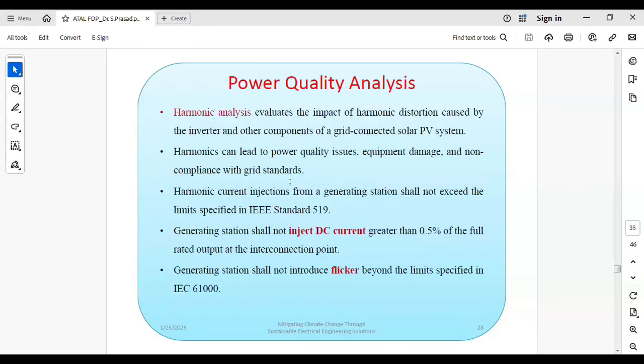And then the next study is power quality analysis. Third one, power quality analysis. Just briefly I'll tell you, due to shortage of time. This is also one of the most important tasks performed by a power engineer whenever the RE developer is going to install a PV plant which will be connected to the grid. So at the point of interconnection, how much harmonics you are injecting into the grid, that has to be verified. A report has to be generated.